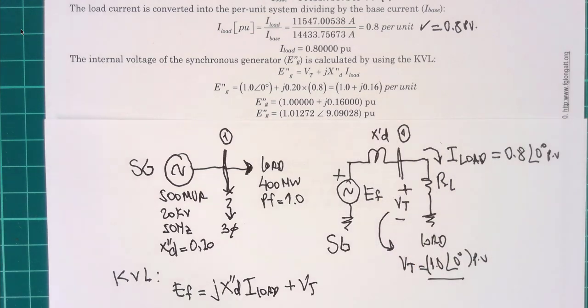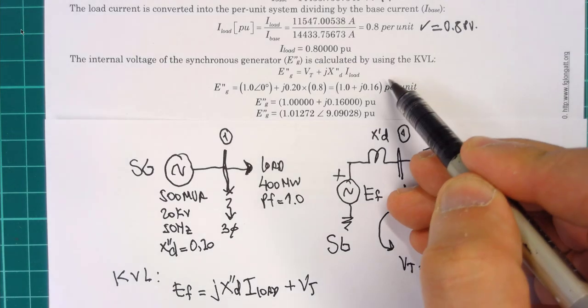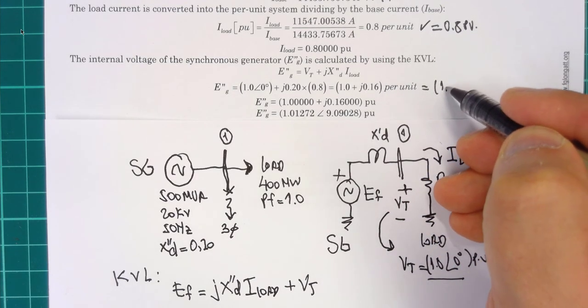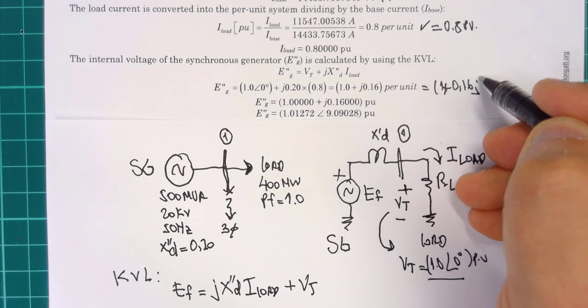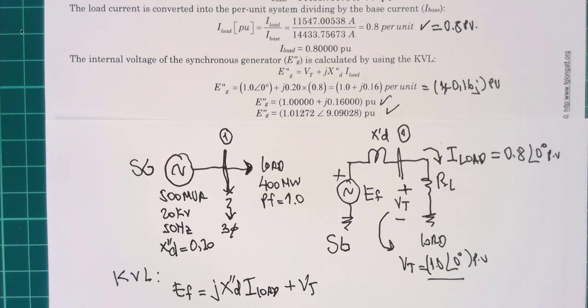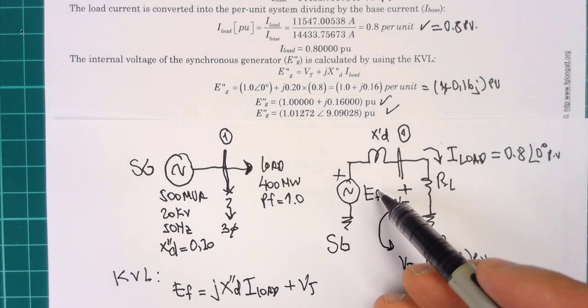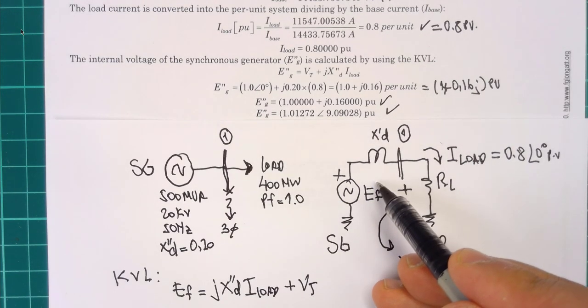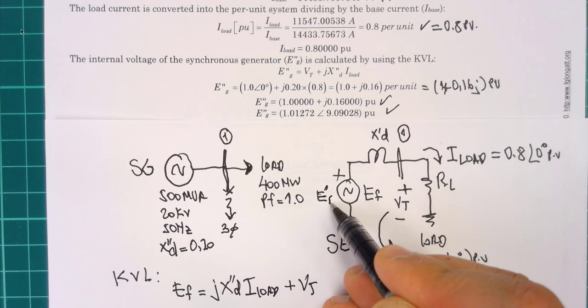Putting the numbers together: E'' = j0.2 × 0.8 + 1∠0°, which numerically equals 1 + j0.16 per unit. Now we know the internal voltage of the generator.